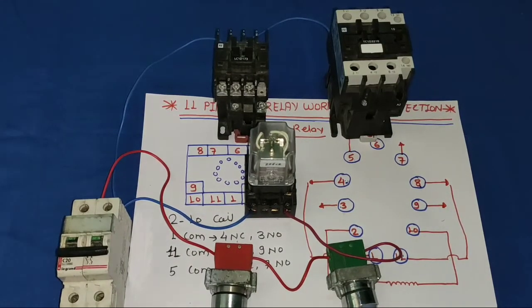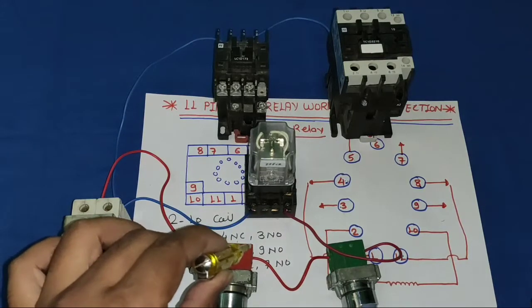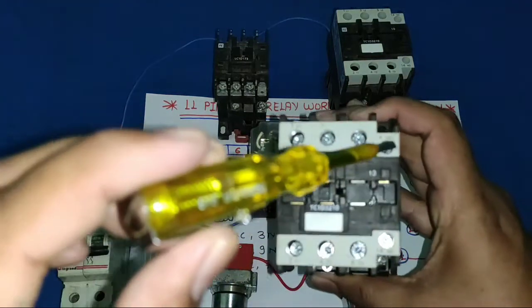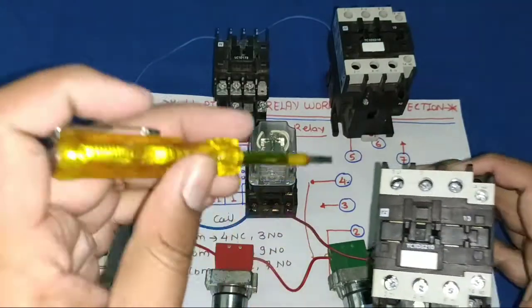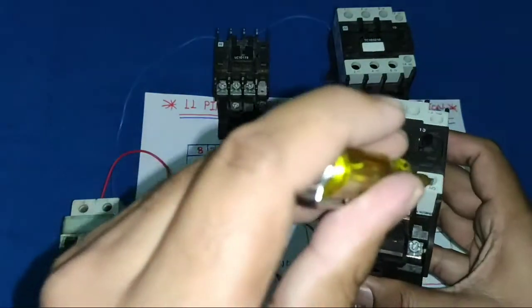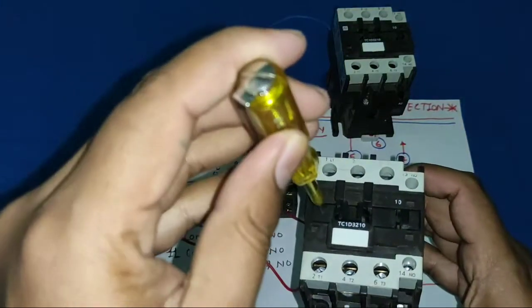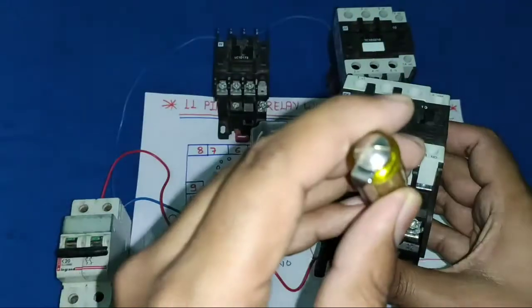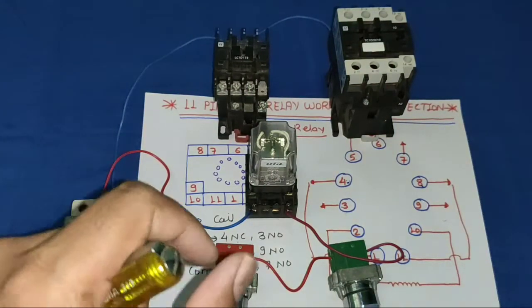Now let's understand how to provide a holding connection. First we understand holding in a starter, then apply the same principle to the glass relay. We take the holding supply from the NO input side. We take a wire from NO input side and connect it to the contactor NO terminal, with a loop from the contactor coil to the NO terminal — as is done in a standard DOL starter. When the contactor operates, this NO makes NC and supply comes through, allowing the contactor to operate permanently.